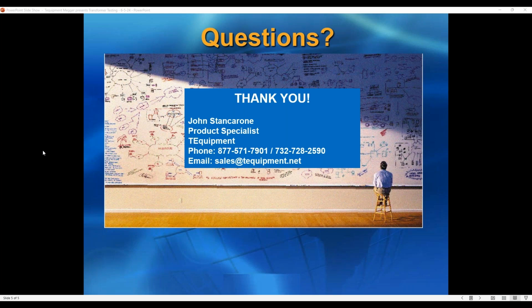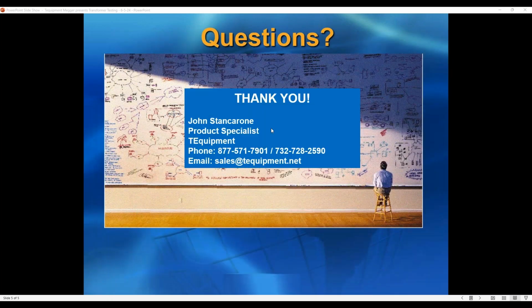Well, yeah, again, talking about turns ratio testing. For distribution transformers, the 8 volts that has been used in the past is sufficient. But as you go up to a little bit bigger pad mounted distribution transformers, maybe 3-phase pad mount distribution transformers, you might need a little bit more. And that is why we have that 30 and 62.5 volts available in the basic and the advanced models of the TTRU1.